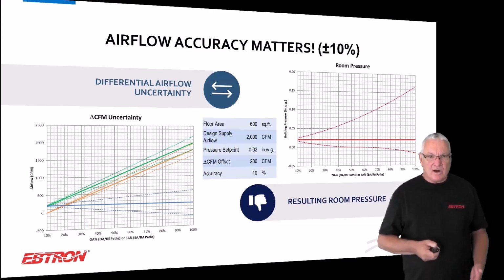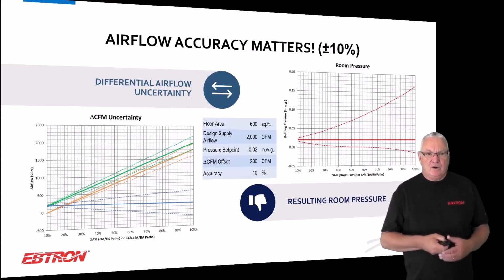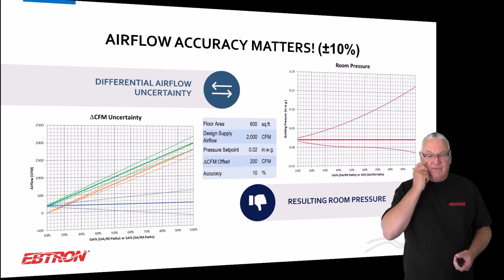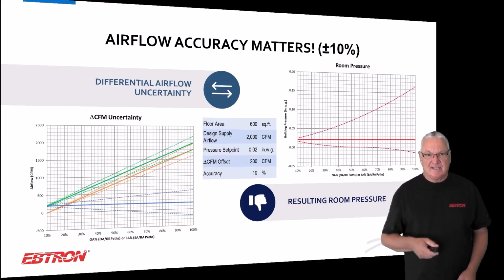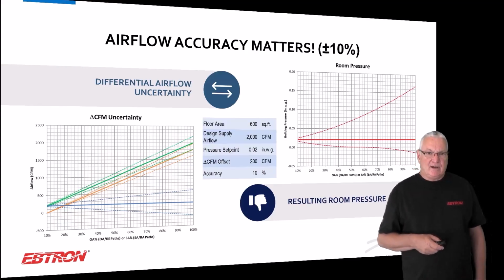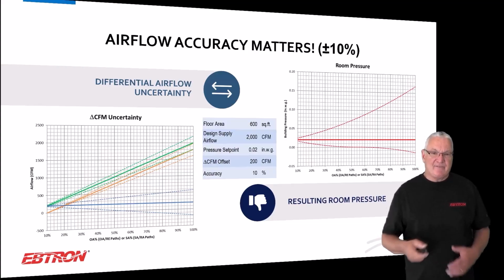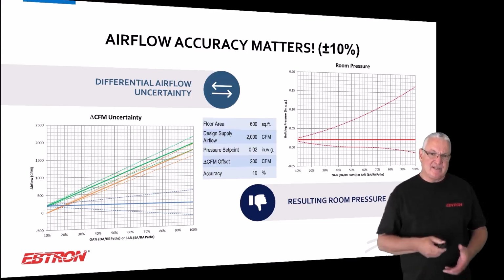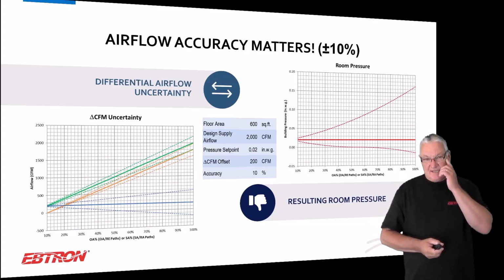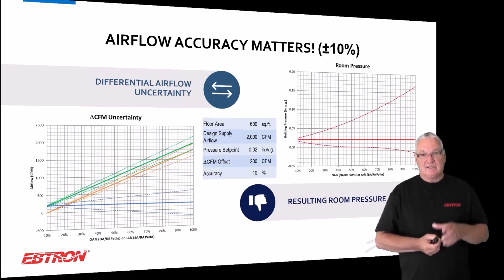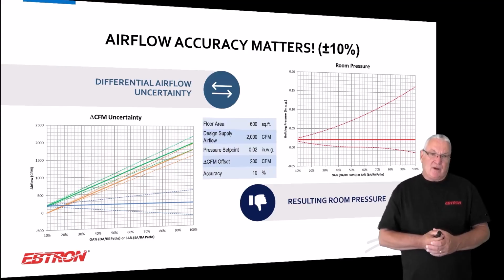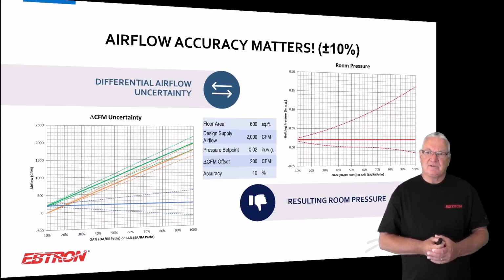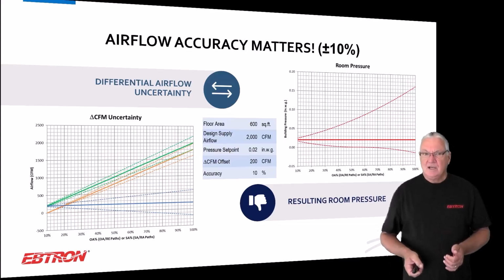So here I have an OR, and I have a floor area. If you go to the middle, I have a floor area, I have a design supply airflow rate, I have a pressure set point, and I have an offset, and then I have an accuracy of the flow measurement. And this is actually a pretty leaky space. But anyhow, I'll show you what happens if your measurement was 10%, which so many people say to me, as long as it's 10%, as long as test and balance gets it within 10%. It's like, no, that's not true.